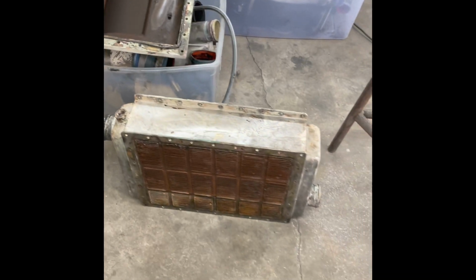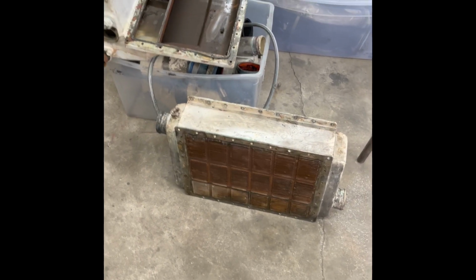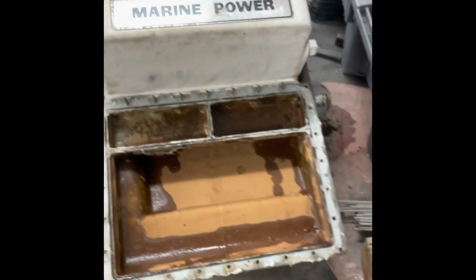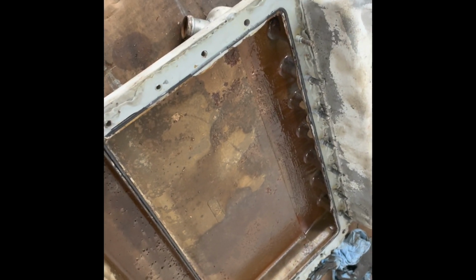There's the core. That's going to be cleaned, pressure tested, and repaired if needed. So this is what we have. This is what they look like when you've gone too long. You see somebody used silicone. They didn't trust those seals. They said, hey, we're going to put silicone around there with them. Well, if you ask me, that's a mistake.